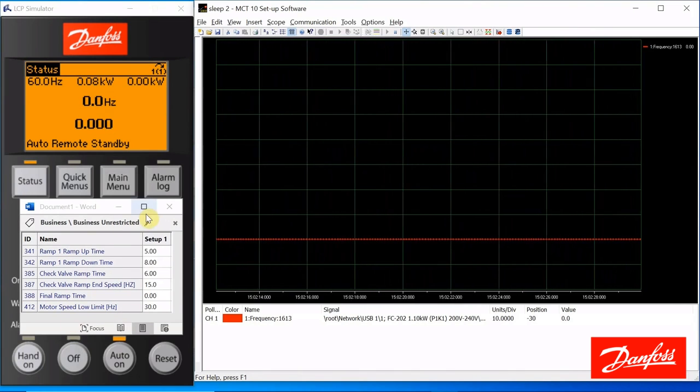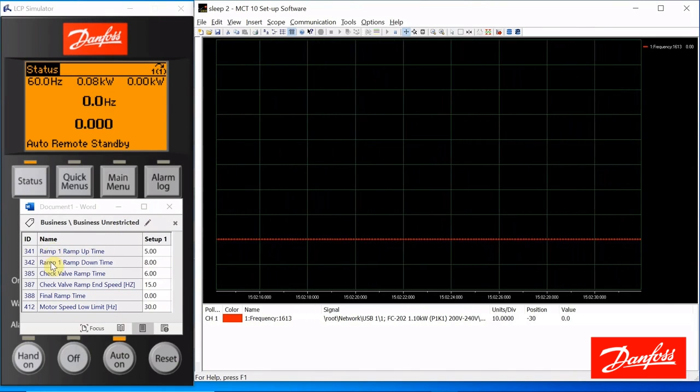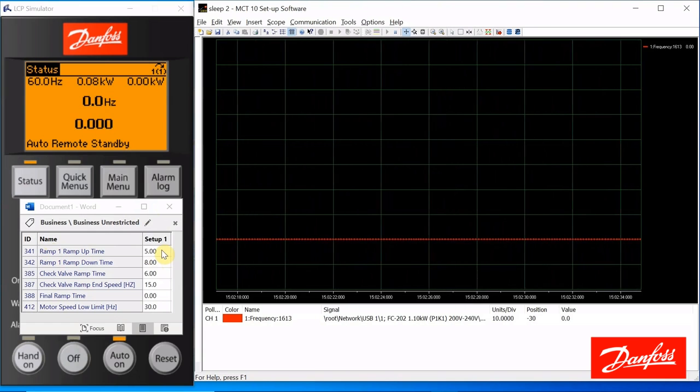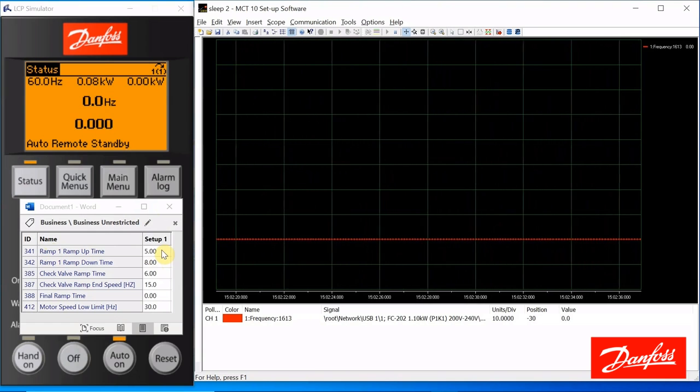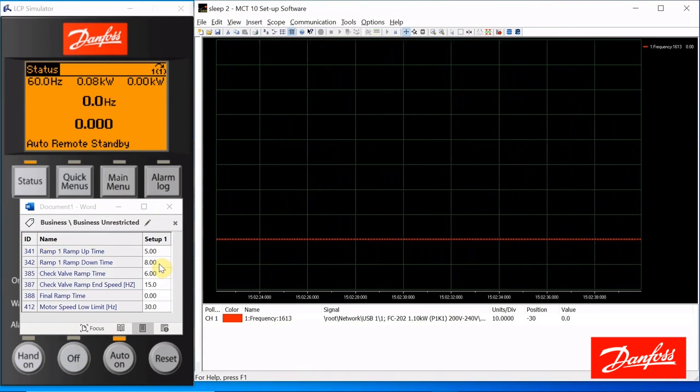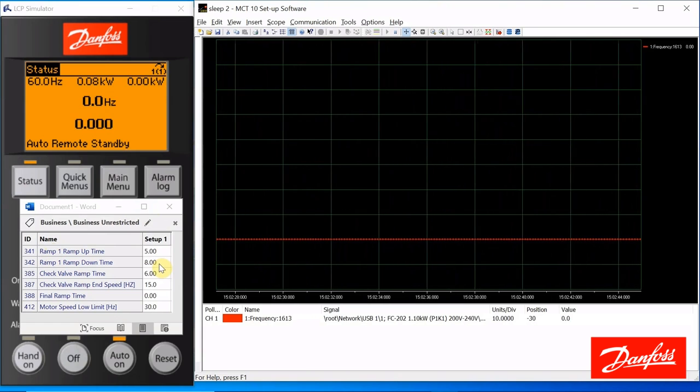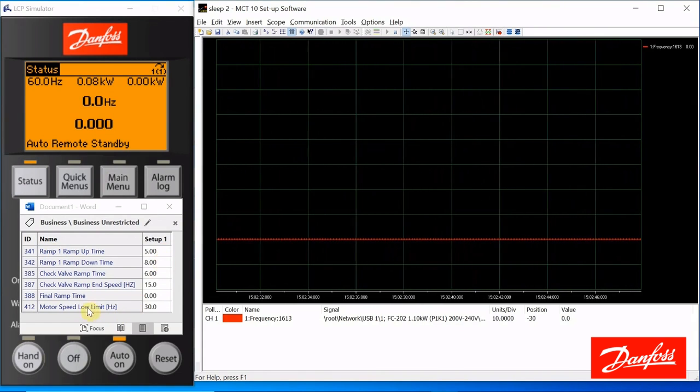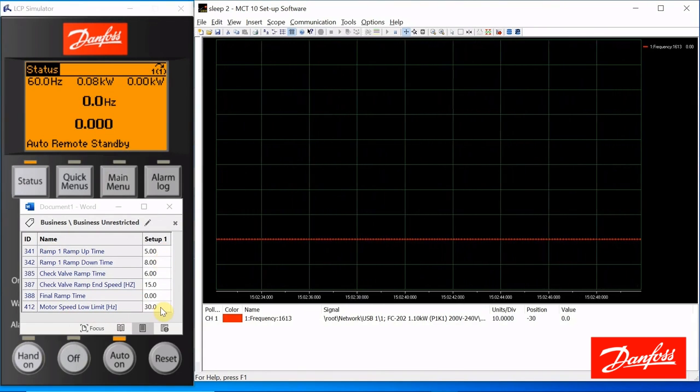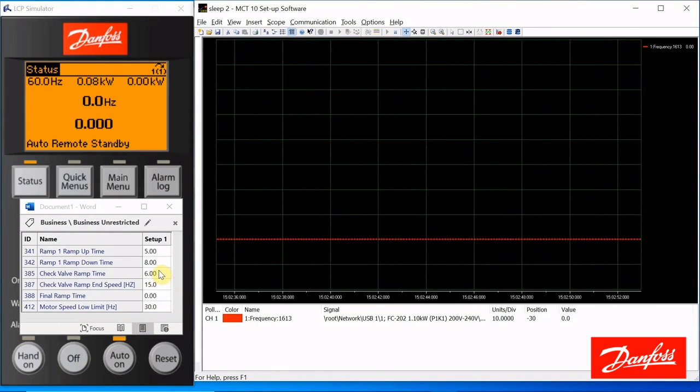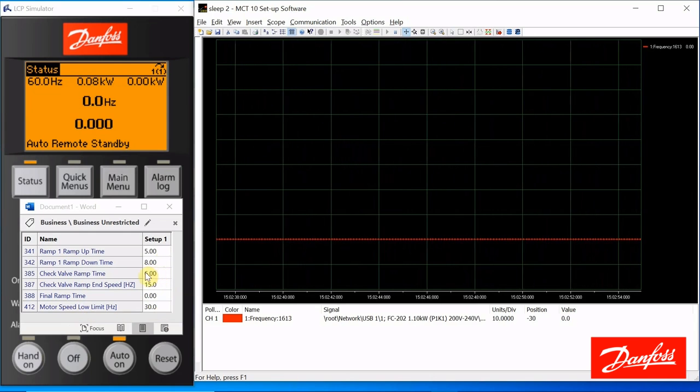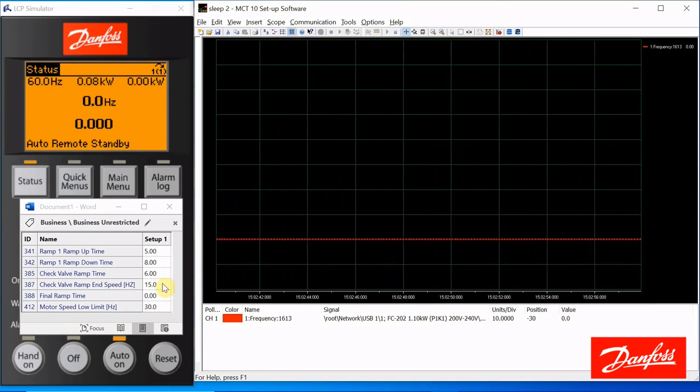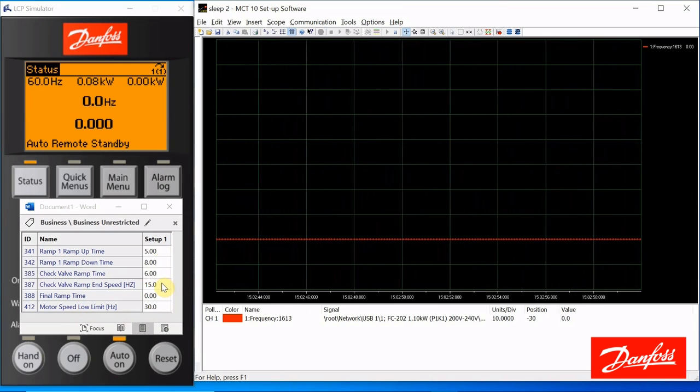Here are the parameters involved. Your normal ramp up and ramp down times. That's the time it takes to get from 0 hertz up to 60. That's the time it would take to get from 60 hertz back down to 0. While ramping down, it'll follow this rate until it reaches the motor speed low limit, at which time it changes over to the check valve ramp time. That's the time it'll take to get from the motor speed low limit to the check valve ramp end speed.